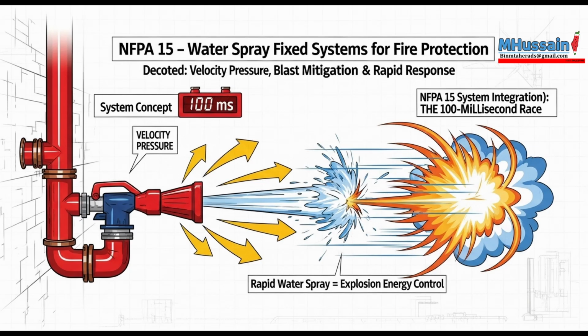And this rate isn't always 0.25, right? It changes for structural steel. It does, based on orientation, which reflects the physics of how water runs off. Horizontal structural members, think beams, tend to hold water a bit better, with less immediate runoff, so they require a lower rate, 0.10 GPM/ft². Okay. But vertical members, like columns, shed water very quickly, so they need the full 0.25 GPM/ft² rate. That's 7.4.3.1 and 7.4.3.4. That difference really highlights the specialization, doesn't it? Precision spray, not just flooding.